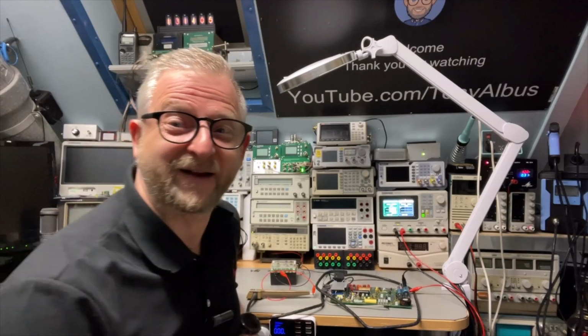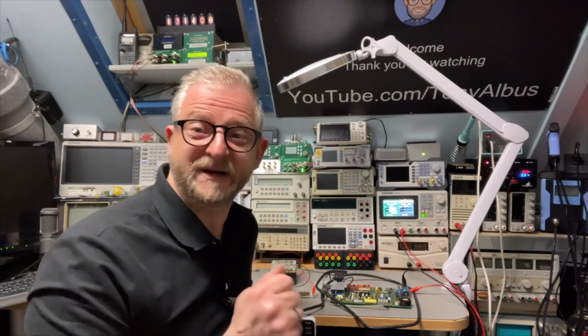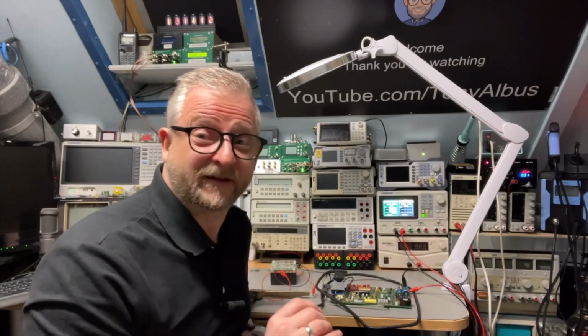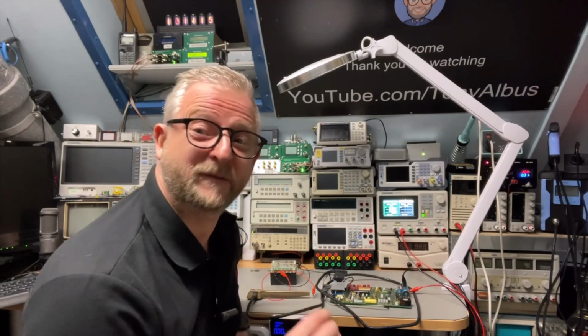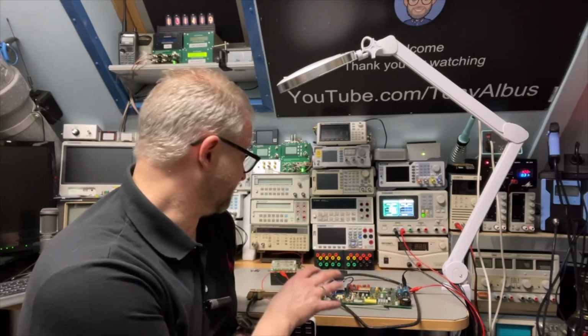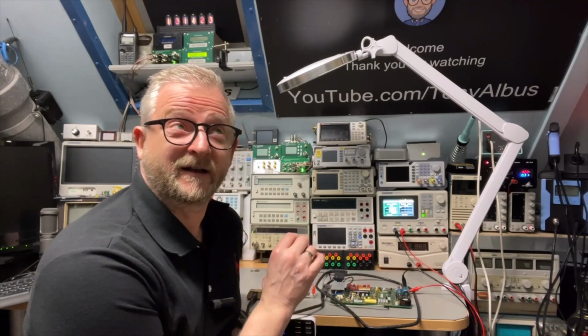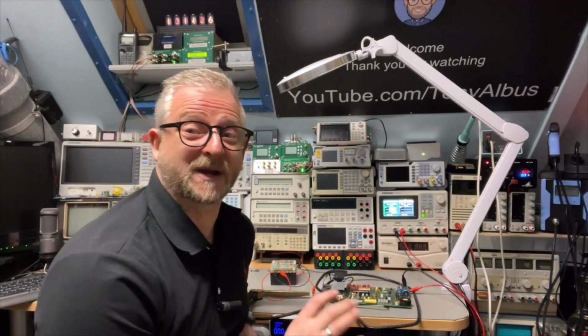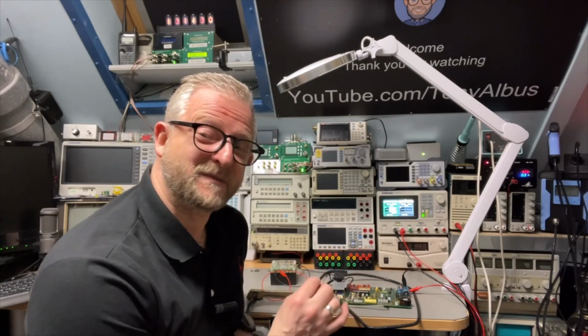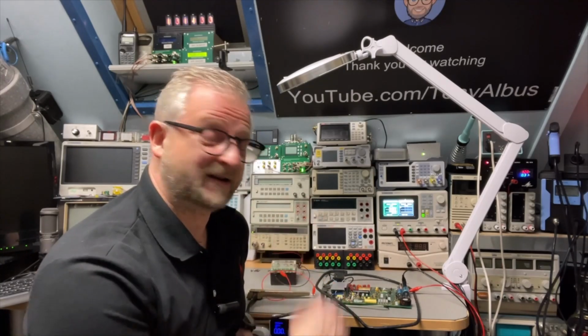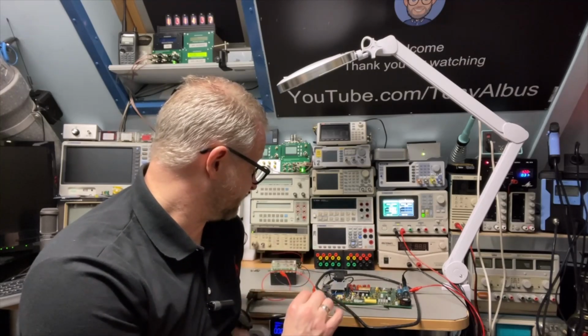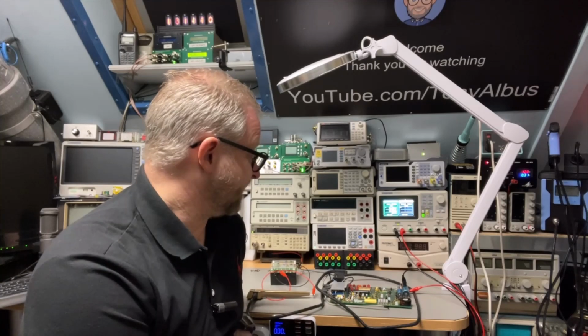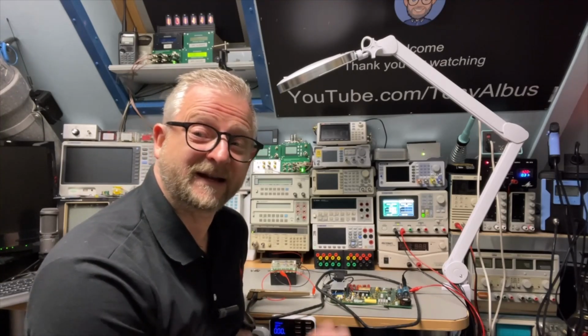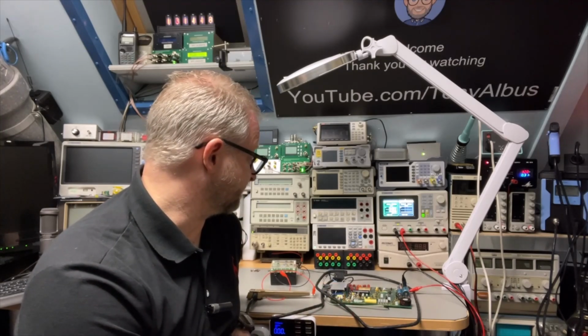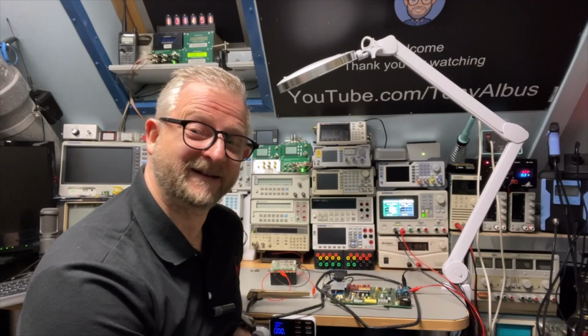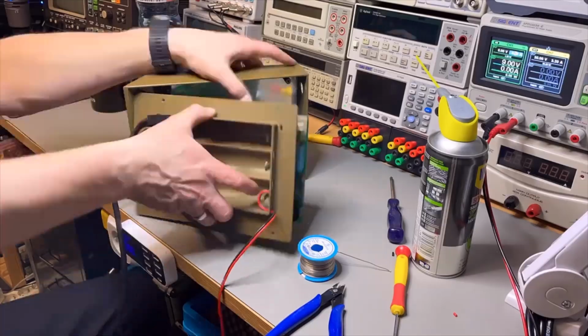So it seems all to be working fine, only not for the AC. Maybe that's just adjusting, or it's cleaning the switches. I haven't cleaned the switches yet, and still the resistance was good, but we've been measuring very low values, and the input impedance of this probe meter is like 55 mega ohms, and usually the multimeters are like 10 mega ohms. So a little bit of dirt, I think, doesn't even bother the meter too much, because it's already that high impedance. But I will clean it, and maybe we get the values a little bit better, and maybe I can even find where I can adjust the AC, so that at least on the 100 Hertz it is correct. But so the person that worked on it actually did fix it for me. Cool.